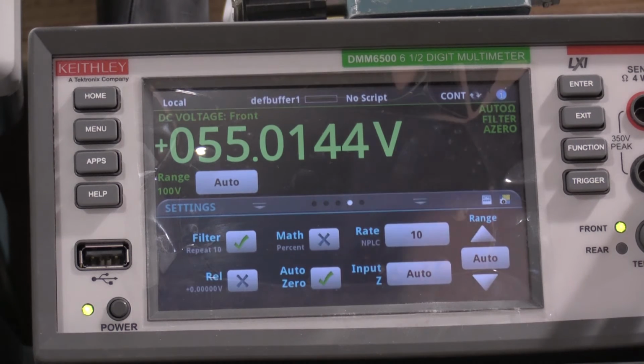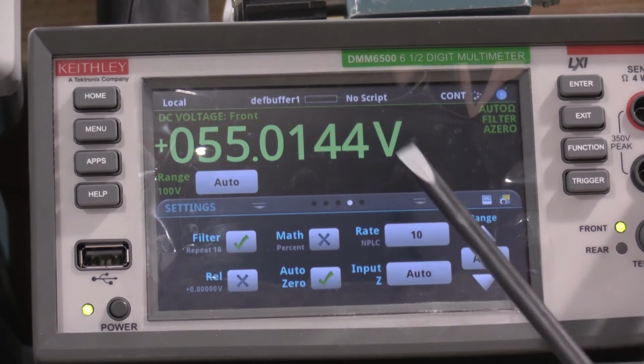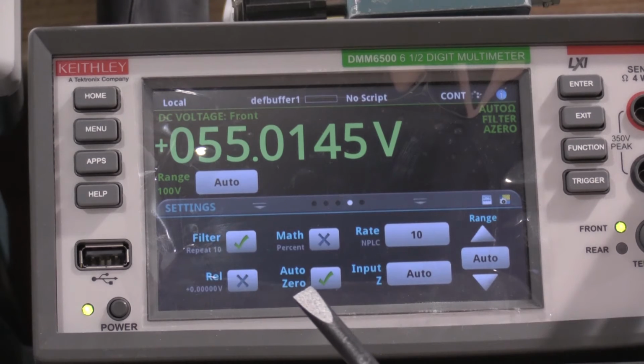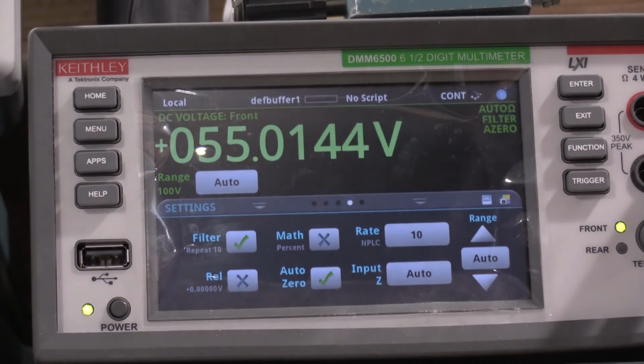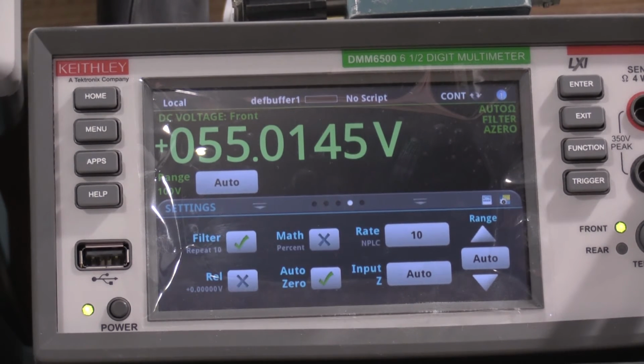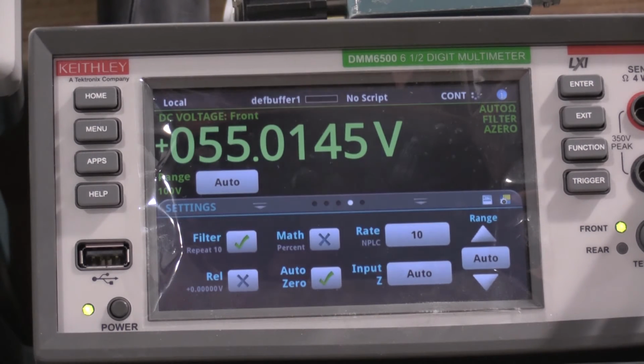Okay, so as you guys can see from the meter setup, we have 10 power line cycles, filters on, auto zeros on, and the variac says we're at 104 volts AC, so the scope is plugged into the variac. Once I get done with the power supply testing, I'll move it to a power strip because then it'll be line voltage for the rest of it. But so that's the 55 volt rail plus 15. Oh, and my tolerance on this is 0.7%. So 5462 to 5539 is what I'm allowed up to. So well in spec.